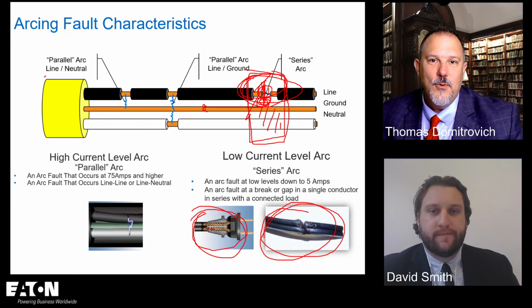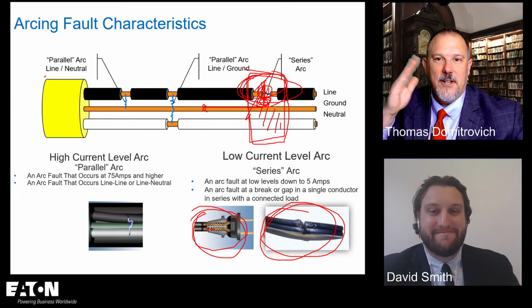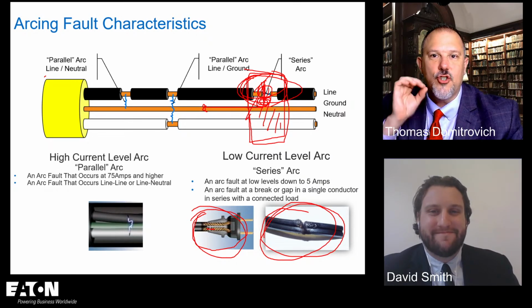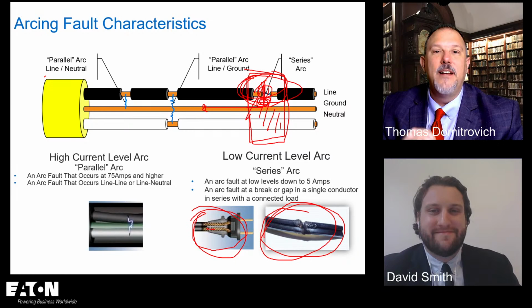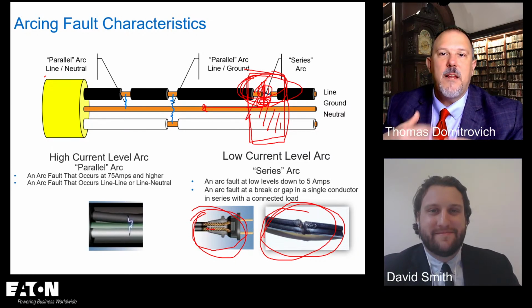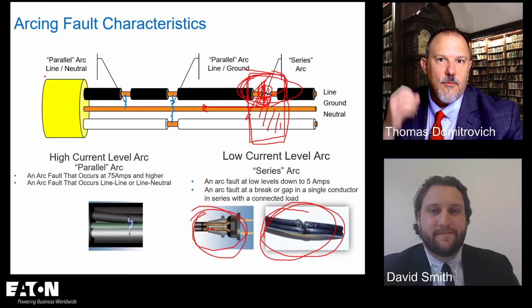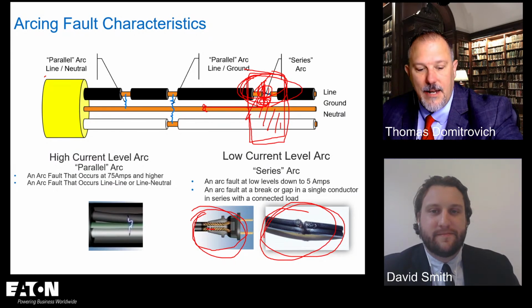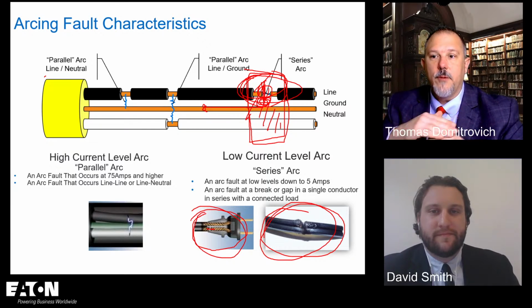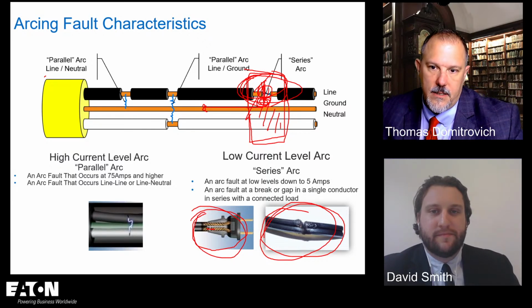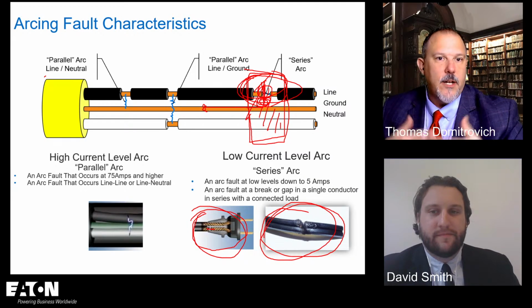And they said you can't use 0 amps as the definitive point to say that something is not energized. And I was like, well, that doesn't make sense. And they said, Tom, put an ammeter on a circuit, and the needle's going to bounce. The numbers are going to bounce. You can never get true zero current. You're always going to get something, even if it's induced. It could be milliamps. You'll never get that meter to read zero. So you've got to come up with a different method. But in any case, that 5 amps also helps us adjust for those types of inconsistencies in metering and measuring and all that good stuff.